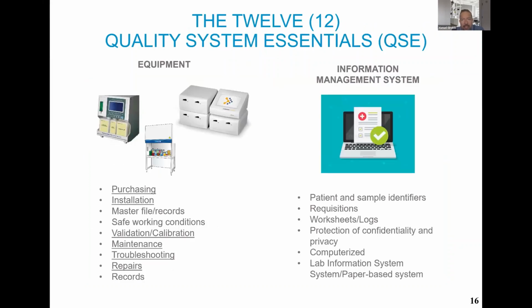All right, the next two essentials are equipment, about purchasing, installation, validation, calibration. Let's keep in mind that I know we have equipment in our labs. That's one of the main components that we have, equipment, reagents, right? And those reagents and equipment must be maintained, must be kept and stored. Reagents might be stored in a proper place, in a lab fridge. And we must document the temperature of that fridge every day, right? And with the equipment, some equipment will need PM, that's the preventive maintenance, that will be done potentially once or twice a year, depending on the manufacturer recommendations.